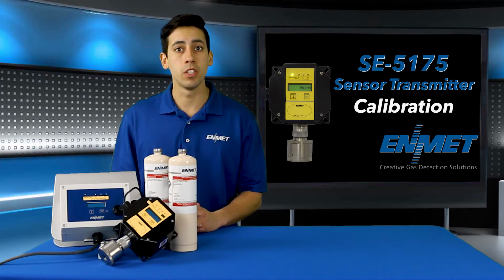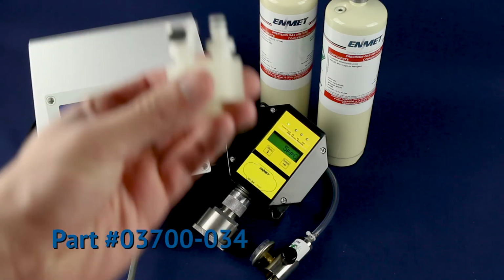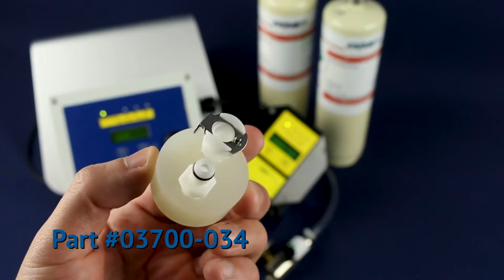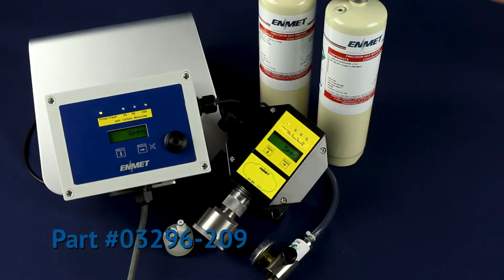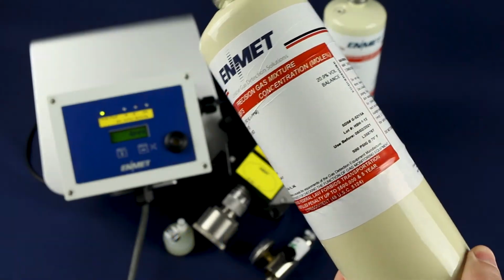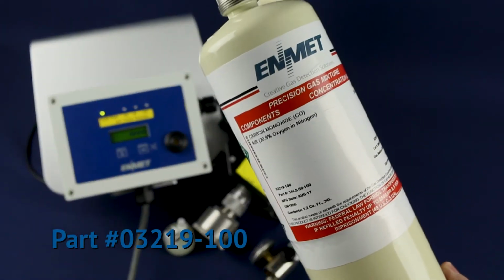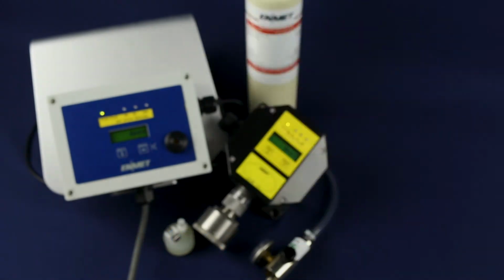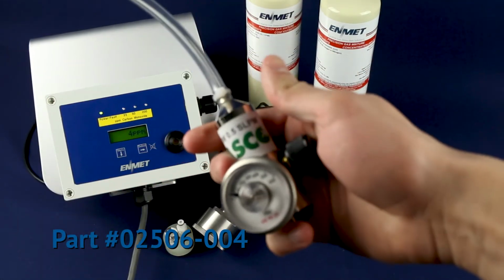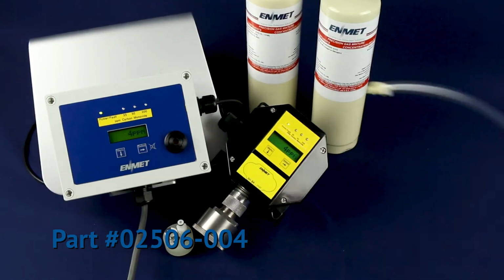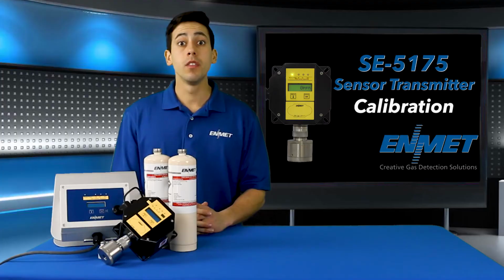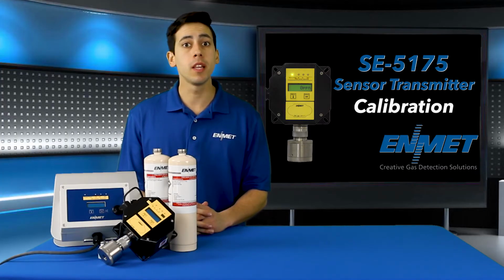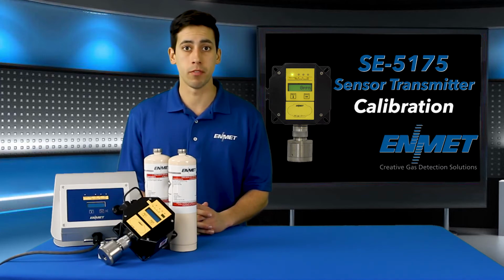You will need the following calibration equipment: a calibration adapter, a zero gas of 20.9% oxygen, a span gas. In this video, I'll be using 100 ppm carbon monoxide, and a regulator. The two calibration cylinders we will be using accept the same 0.5 liter per minute regulator. The zero function must be performed by exposing the SE-5175 sensor to clean air. If the ambient air is in question, use a cylinder of 20.9% oxygen to provide a clean air reference.